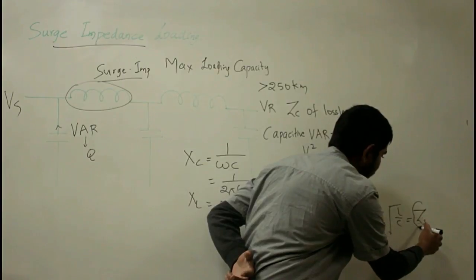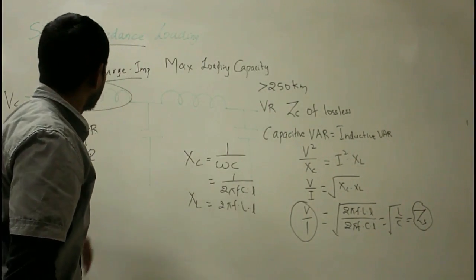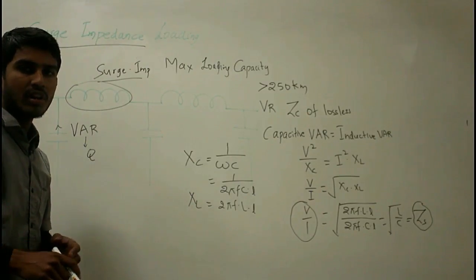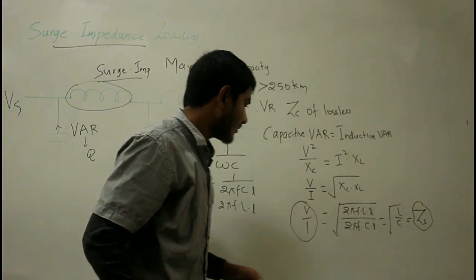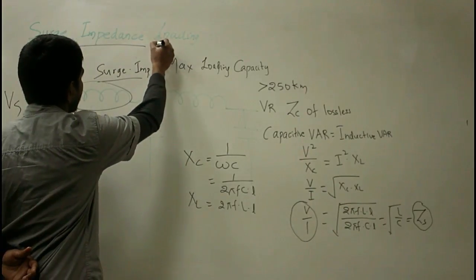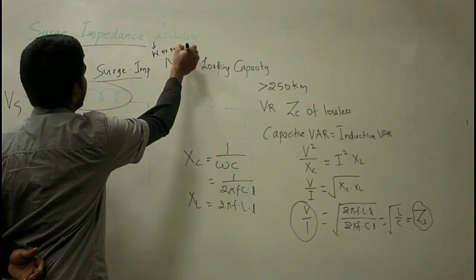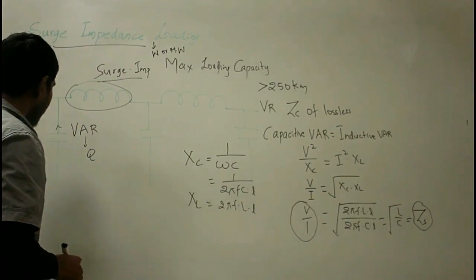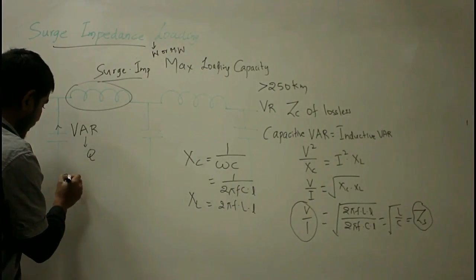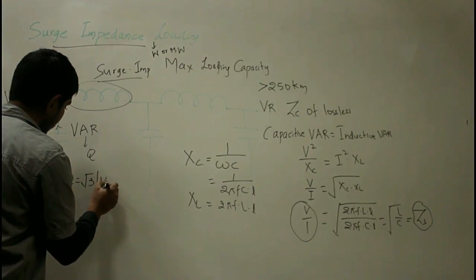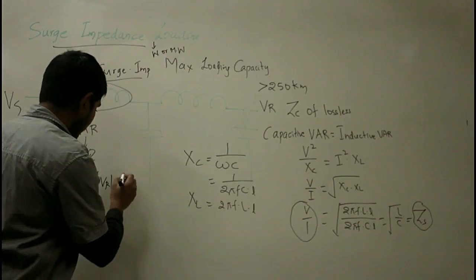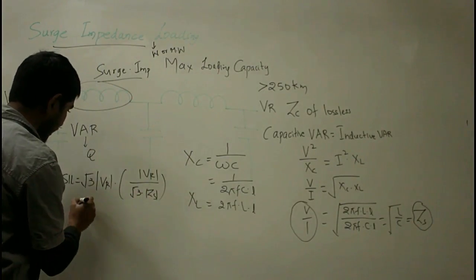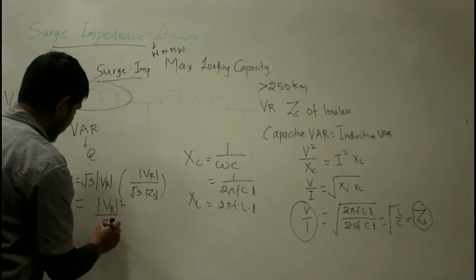Surge impedance loading (SIL) is defined as the power delivered by a line to a purely resistive load which is equal in value to the surge impedance. The units of SIL may be watts or megawatts. Calculating the power delivered: SIL = √3 × VR × (VR / (√3 × ZS)) = VR² / ZS. This is the surge impedance loading formula.